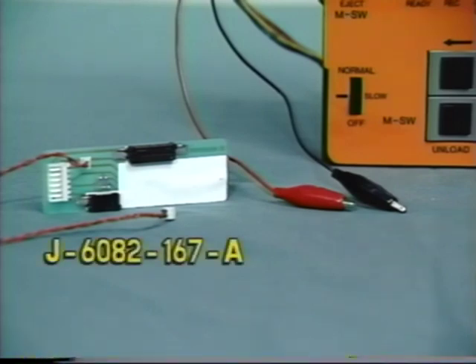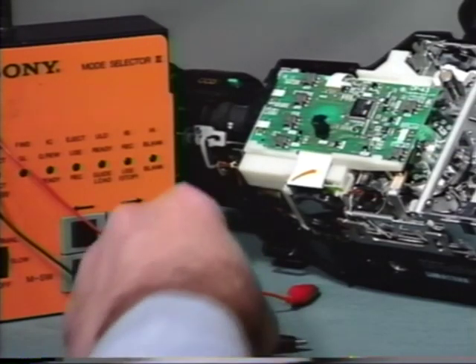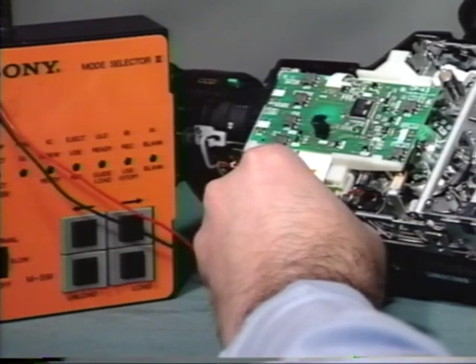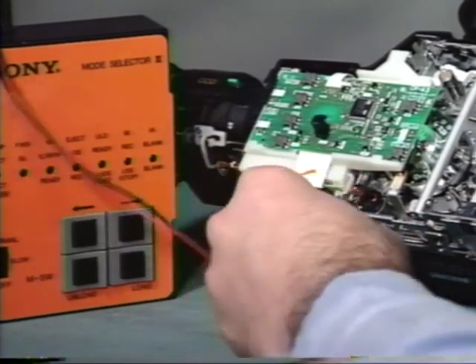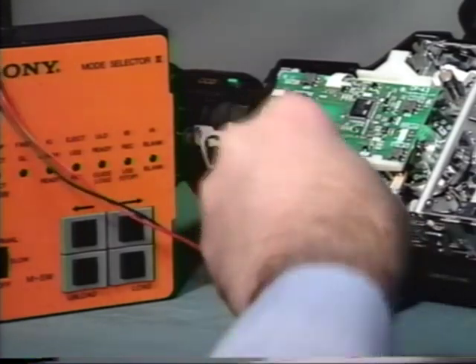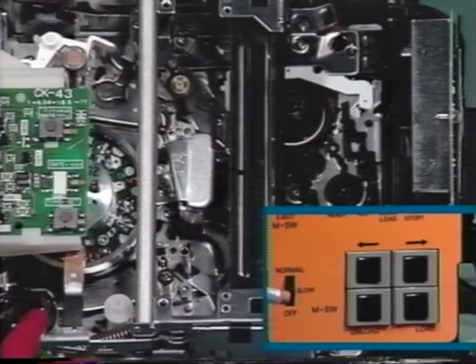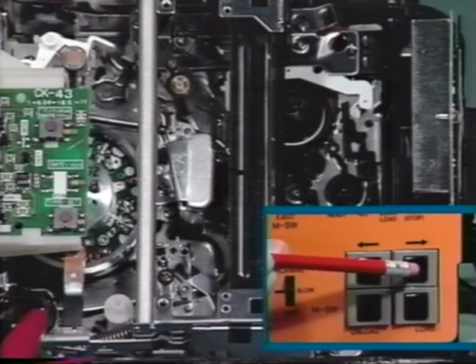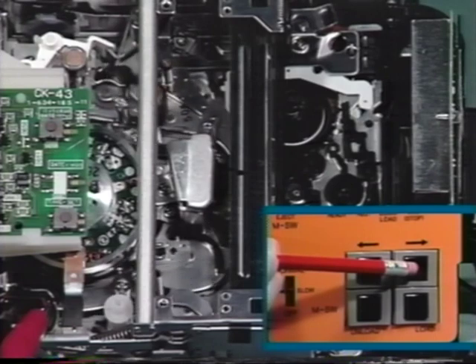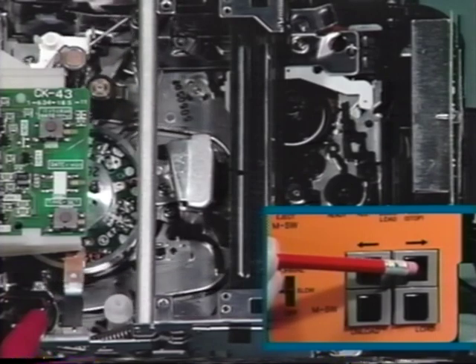For some units, the mode box adapter board can also be used to connect it to the loading motor, as well as provide information about transport position. Because our unit is only partially disassembled, the alligator clips are used. Connect them to the loading motor. Once connected, flip the speed switch to the normal position. You can drive the motor forward and back by pressing the upper load and unload buttons.